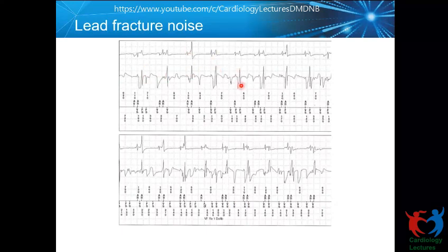In between that, you find an artifact because the electrode has fractured, and these are the make-break signals that you're seeing, which is very typical of the make-break signal when there is a lead fracture. Of course, the impedance will be higher, and you can corroborate that with this noise.